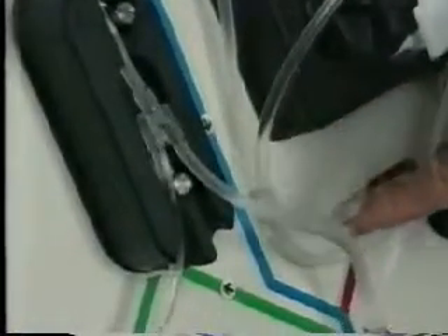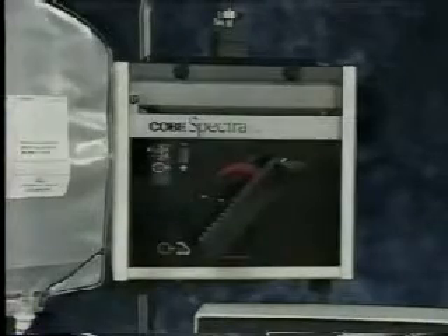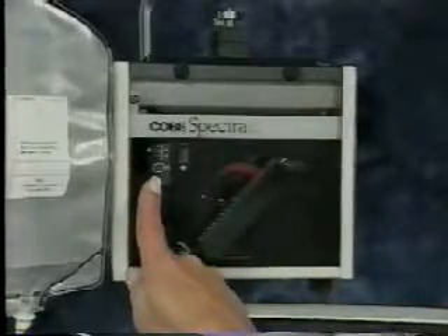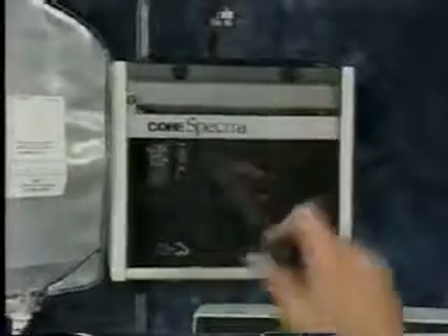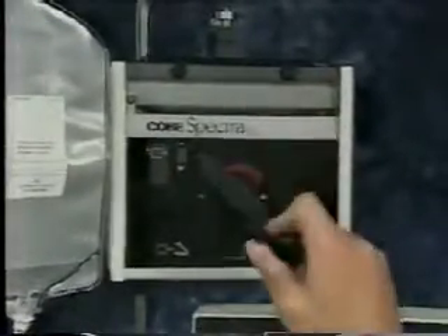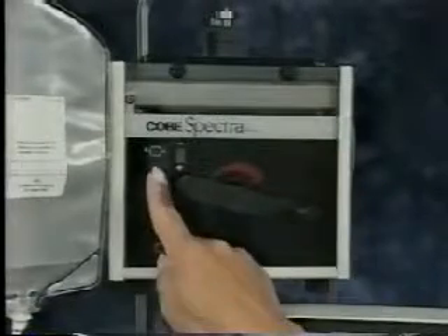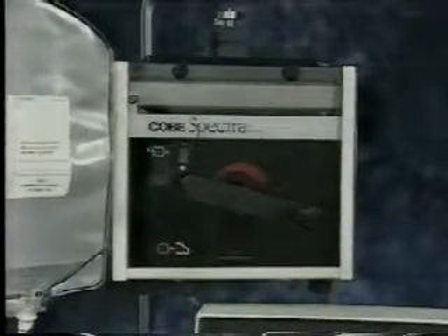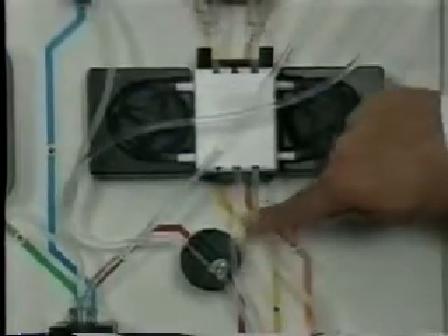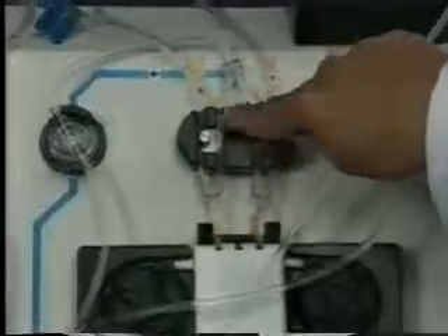You were troubleshooting the alarm that read return pressure sensor did not reach alarm limit. Let's review some of the possible causes for this alarm. One possible cause is misloaded tubing. Once you have corrected the problem, press Continue to clear the alarm. Let's look at another possible cause for this alarm. The return flow controller may not be fully up in the prime position. This alarm will also occur if the return pressure sensor is not placed properly in the sensor housing.